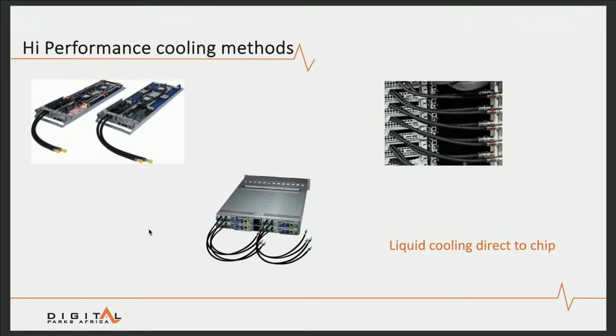It's essentially a traditional cold water, hot water circuit that reaches the chip on the board through a system of small rubber pipes. There you see a picture of it, actually, how it comes out the back of the chassis, and essentially once the chassis are all stacked together in a rack, it connects to the back of the rack, and on the back of the rack you then have your cold and hot water pipes running through the data center. This technology is quite efficient, but it's quite expensive as well.